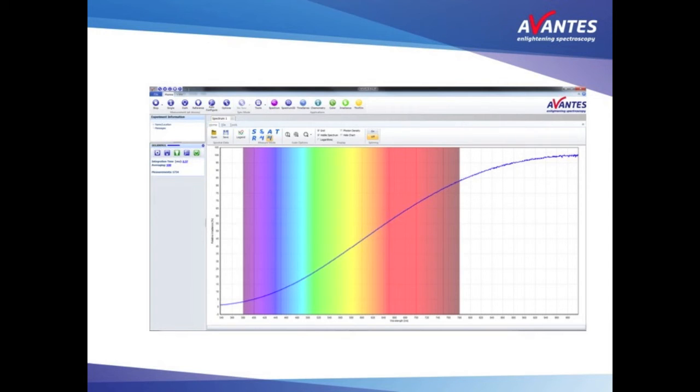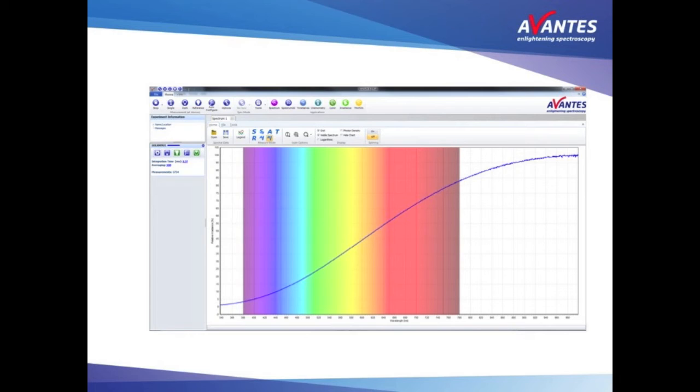If intensity information is important to be weighted, it is possible to have an irradiance calibration done on your spectrometer system and view the spectrum in the IA mode, which stands for absolute irradiance mode. However, if one wants to save these additional costs for calibration but needs to know the intensity relationships relative to each other, the relative irradiance mode can offer you a solution.